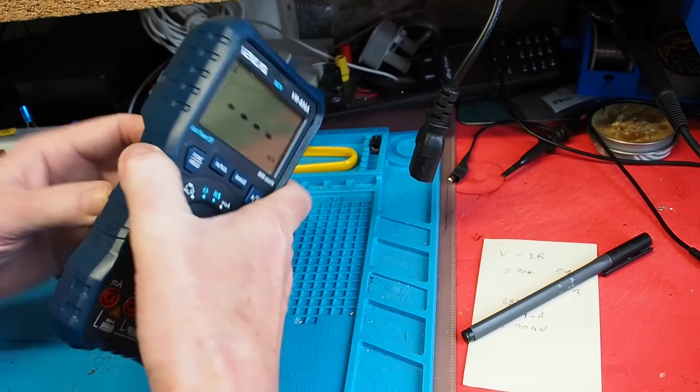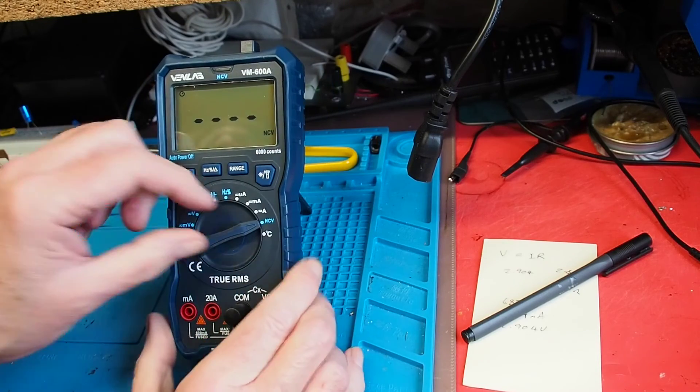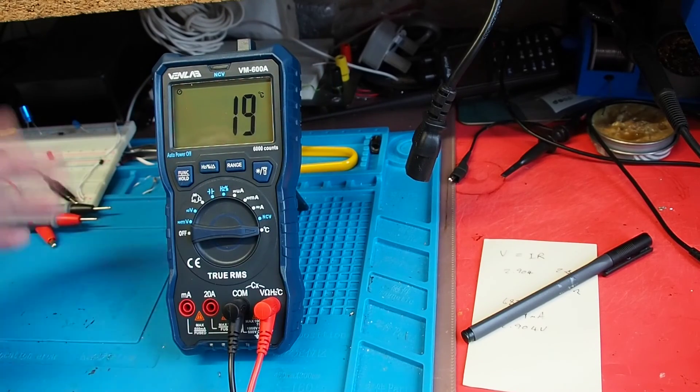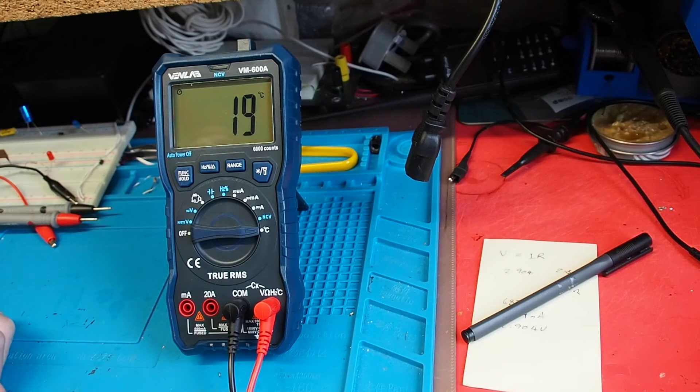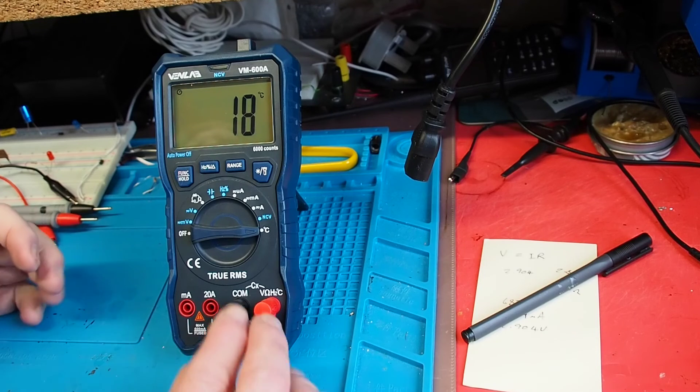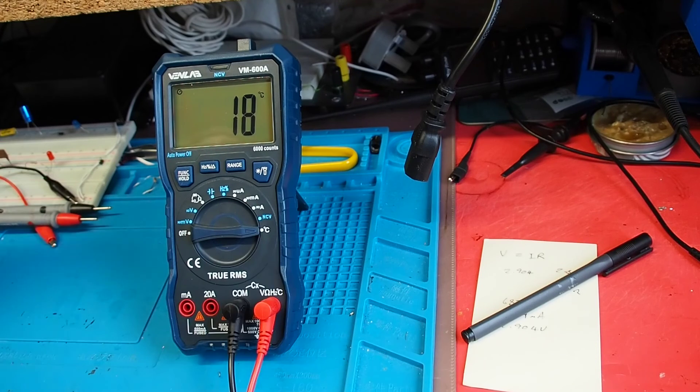Switching to temperature gives us the ambient temperature, obviously the internal sensor for the meter. Included with the meter there is a thermocouple which you can attach here which would give you external temperature reading.